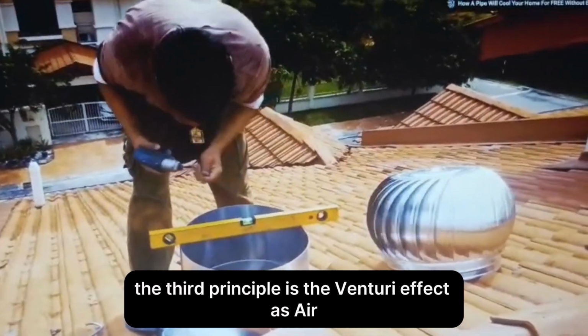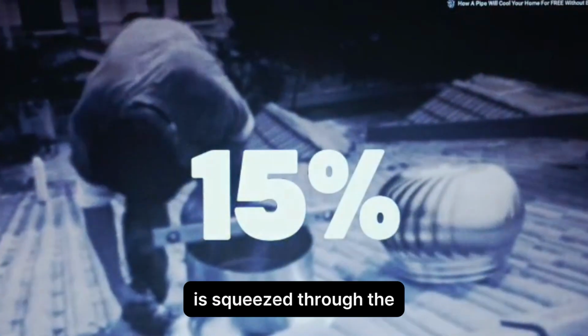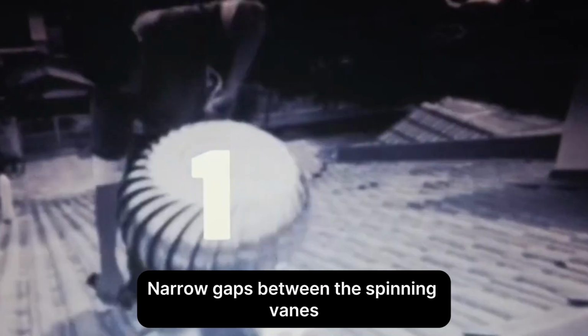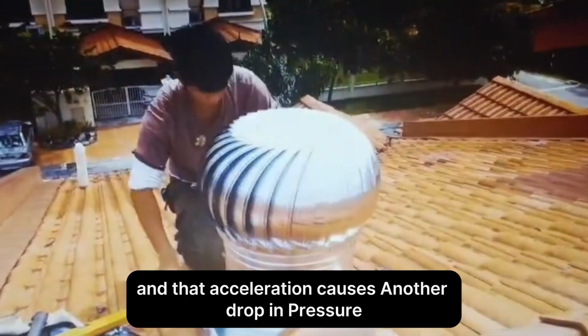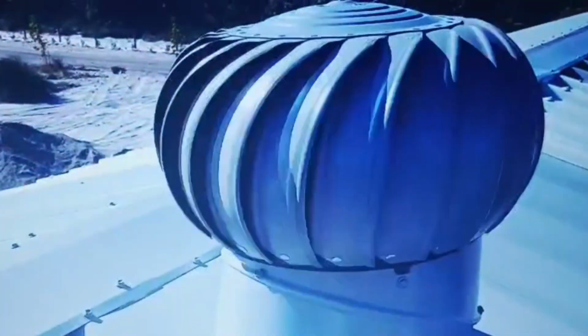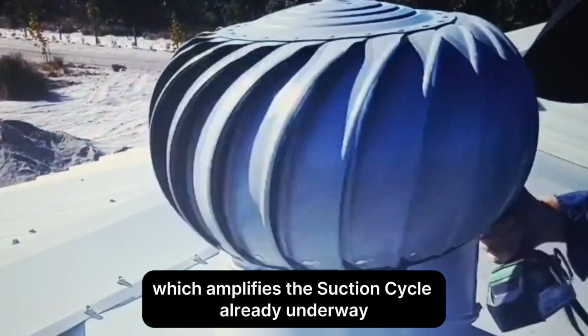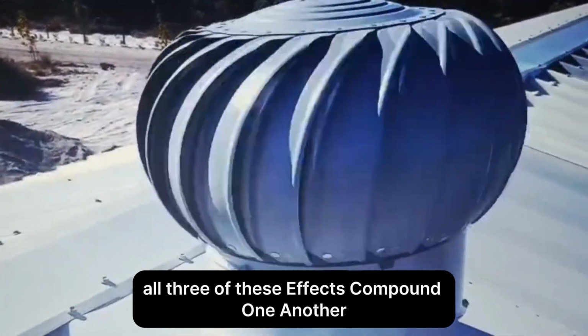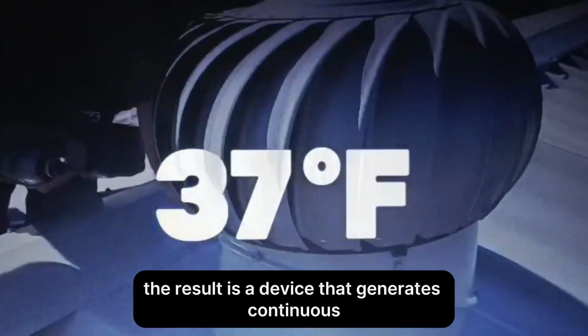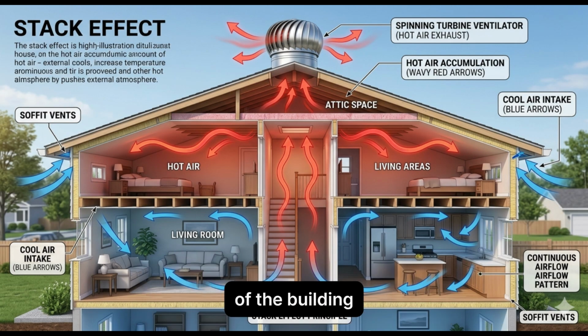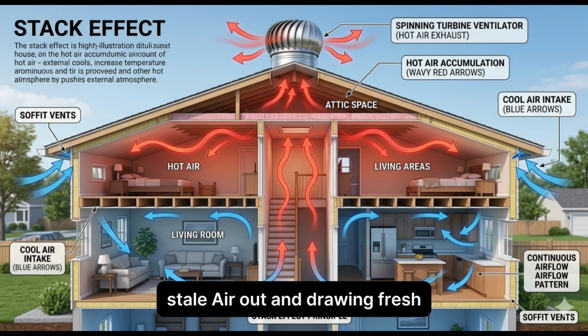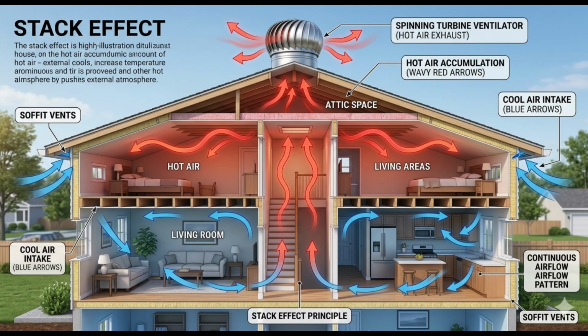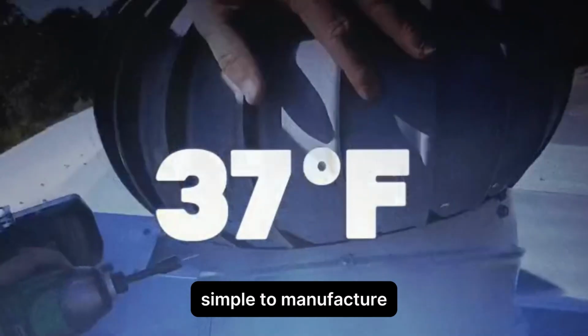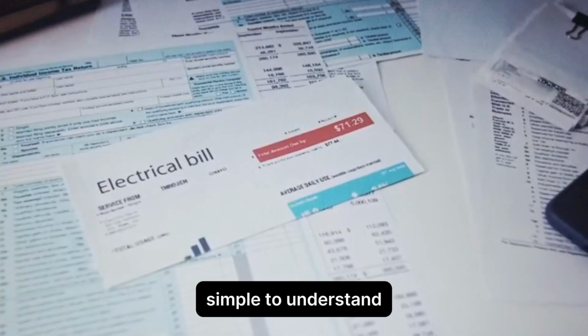The third principle is the Venturi effect. As air is squeezed through the narrow gaps between the spinning vanes, it accelerates further, and that acceleration causes another drop in pressure, which amplifies the suction cycle already underway. All three of these effects compound one another simultaneously. The result is a device that generates continuous negative pressure at the single highest point of the building, constantly pulling hot, humid, stale air out, and drawing fresh, cooler air in through the soffit vents below. It is elegant engineering, simple to manufacture, simple to install, simple to understand.